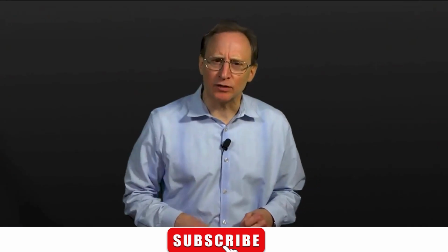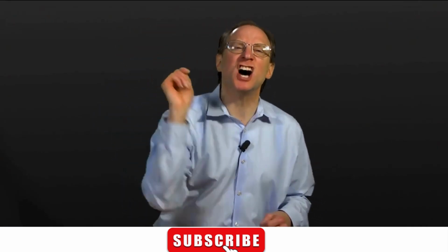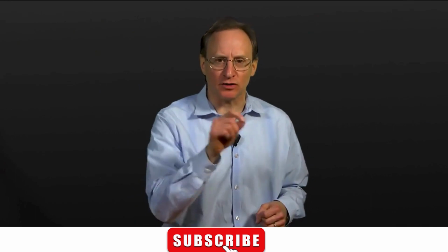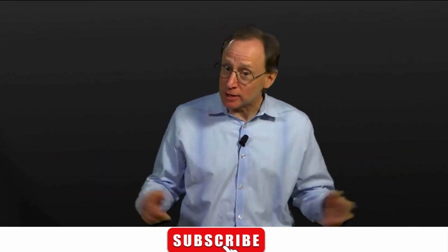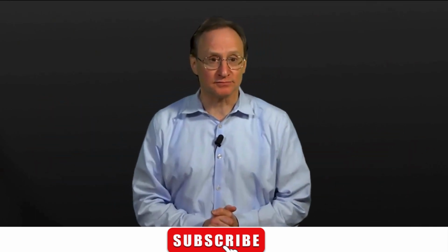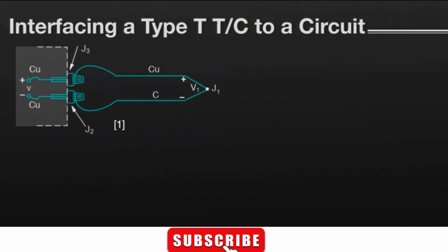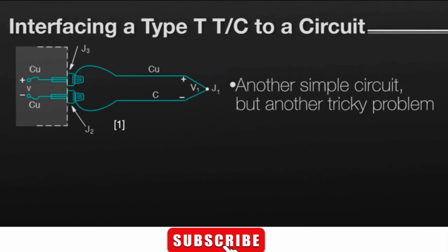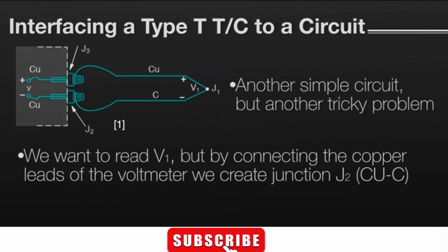The feedback I got was that you guys said you love those circuit diagrams for RTDs. Okay, well, here's some more for thermocouples. Let's start by trying to measure the thermoelectric voltage of a type T thermocouple. Should be simple, right? We would like to read V1, the thermoelectric voltage produced by heating junction J1, the intersection of a stretch of copper and Constantan wire.